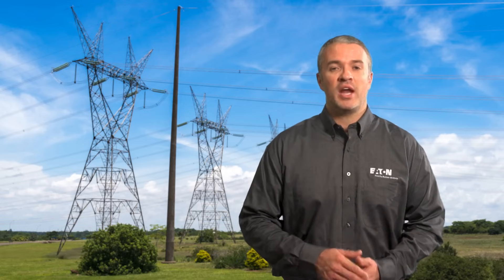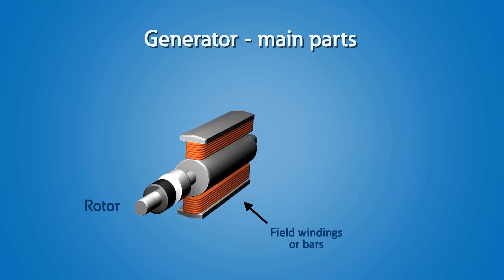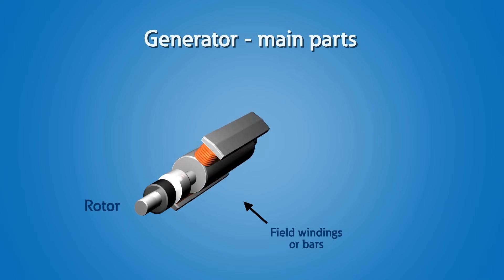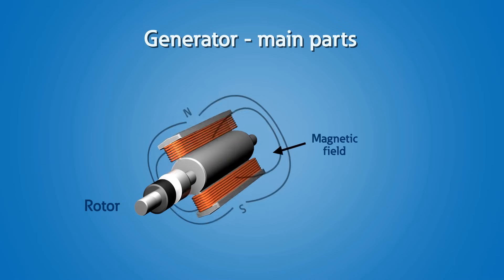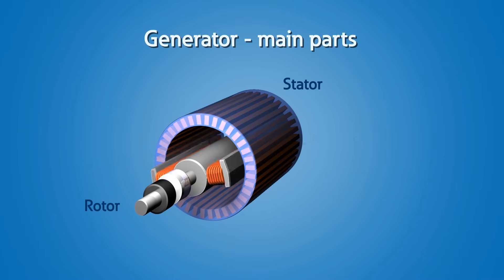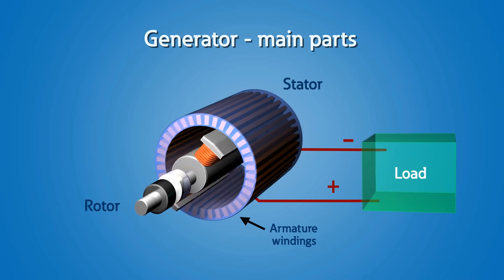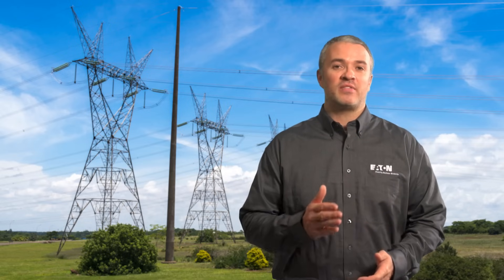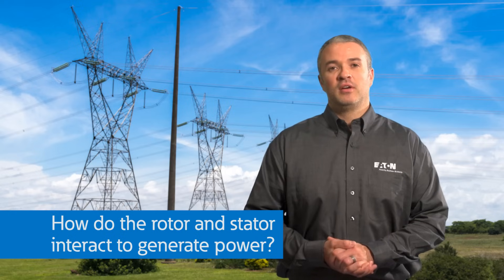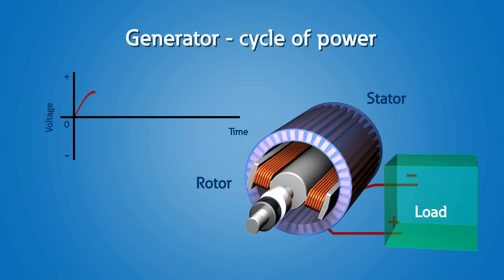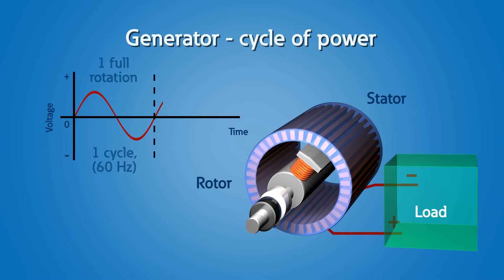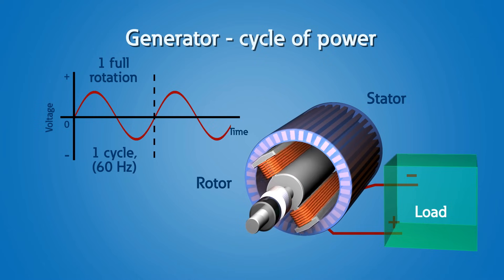The two main parts of a generator are the rotor and the stator. The rotor is the part that rotates and consists of many loops of copper wire or bars called field windings. Field windings are used to create the magnetic field induced on the metal core to which the wire is wrapped around. The stator is the stationary or static part of the generator that consists of copper windings called armature windings. The power produced by the generator will flow out of these armature windings towards the load.